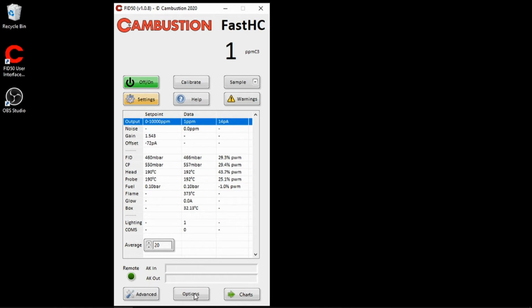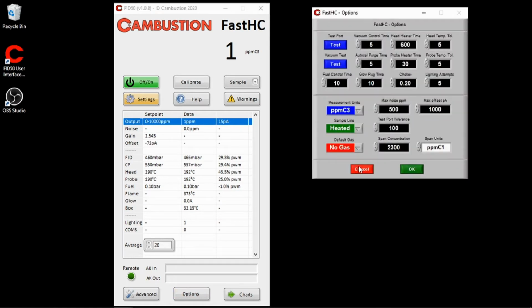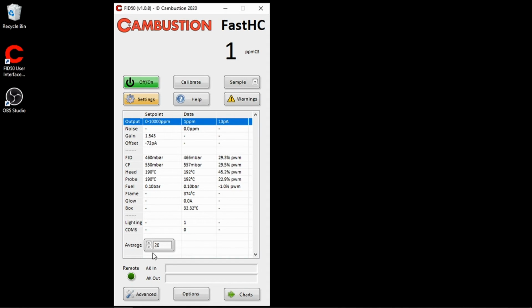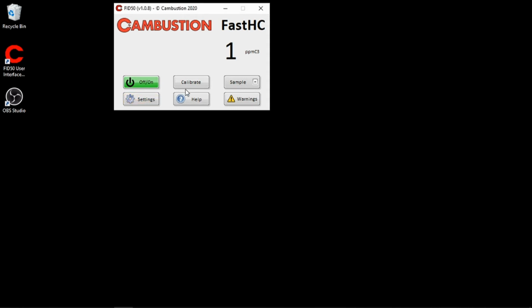If I press the options button, this will allow us to enter the calibration gas that we're using. At the moment it's set to 2300. We can change that to 1900 parts per million, and we can also change the span units that are used. So we know that we are 1900 parts per million propane, so we'll change that. In this window as well, you can change the measurement units which are displayed, so we've also set that to ppm C3.